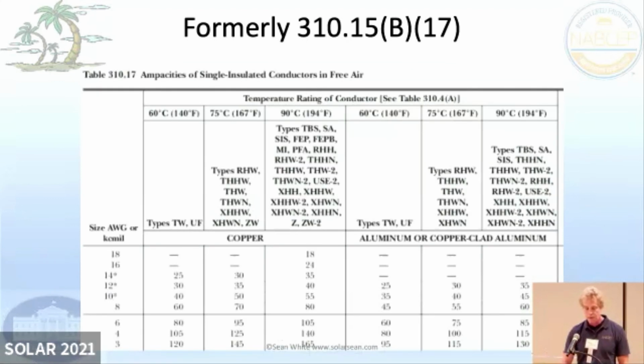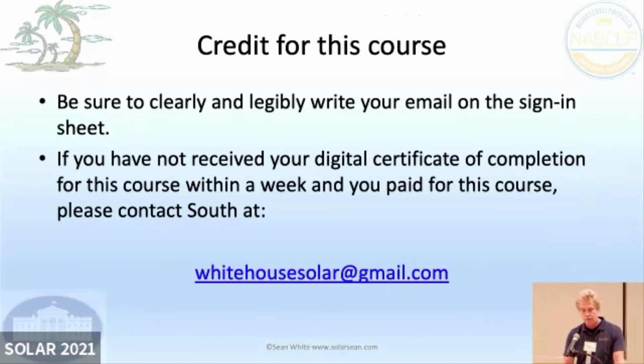310.15(B)(17), which is now 310.17. And that last one was for wires that were not hanging in free air, not single conductor cables. But with PV, sometimes we have single conductor cables in free air, like behind the PV array. And those single conductor cables in free air get cooled off by the air as the air blows by it. Perfect timing for credit for this course.